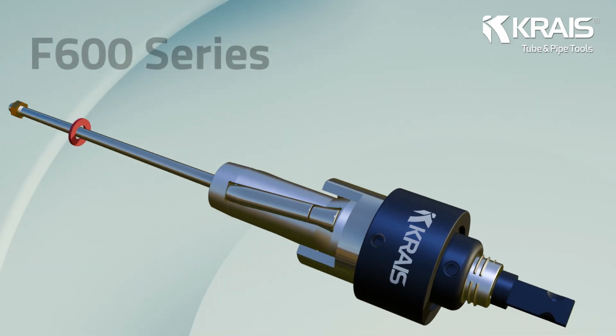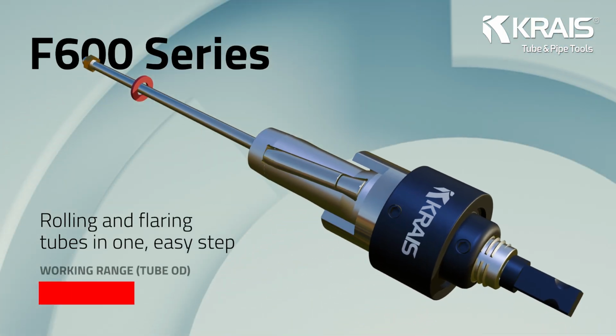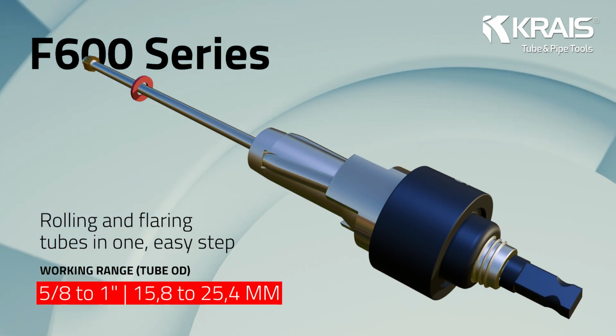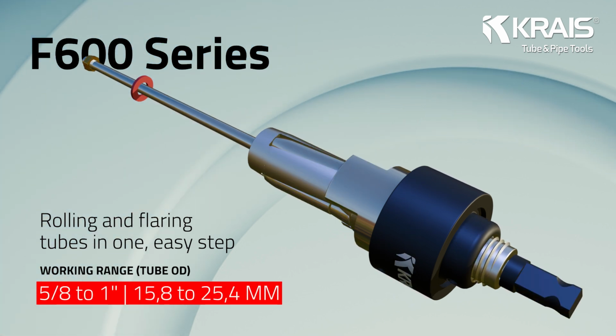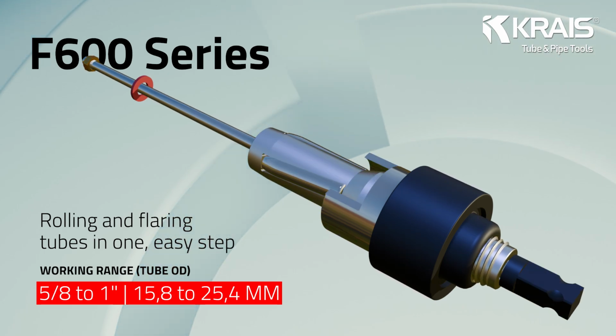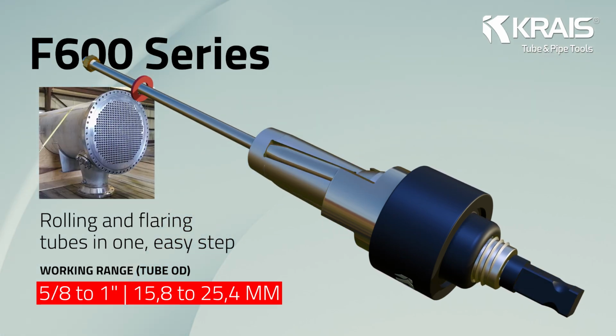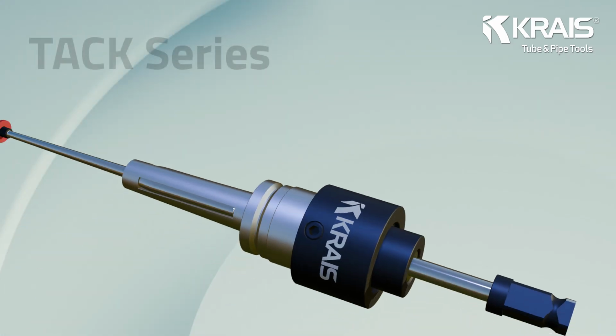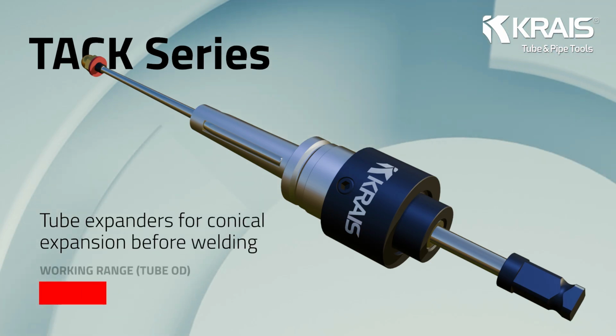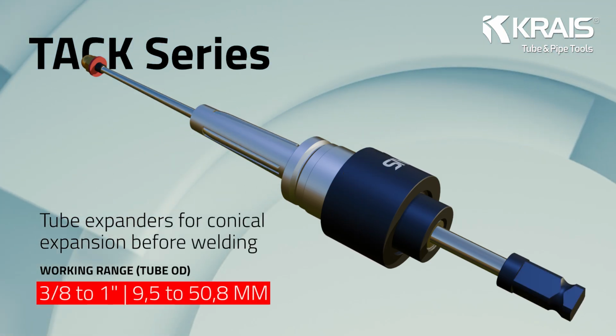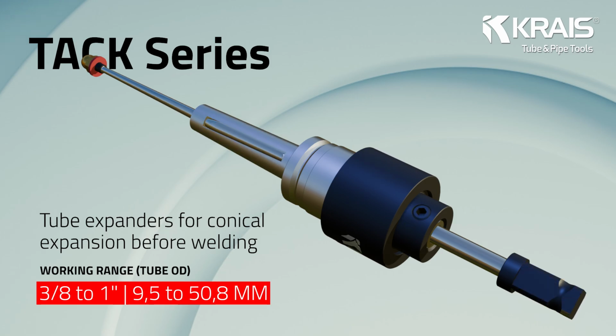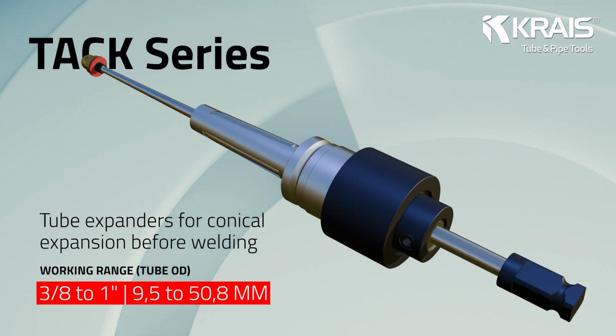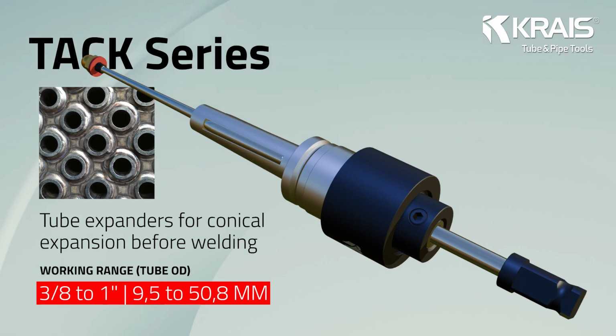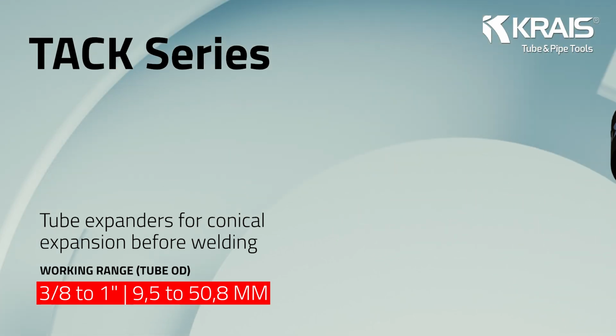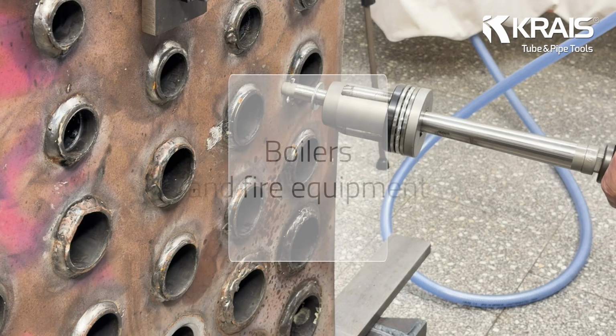The KRAIS F600 series performs tube expansion and end flaring in a single operation. Use it where the specification calls for a flared tube end as a mechanical feature, or where you want to avoid variability associated with a separate flaring step. The KRAIS TACK series delivers short, controlled, conical expansion as preparation for welding. It is used in rolled and welded joints to remove clearance, stabilize the tube, and improve weld conditions. The conical profile provides maximum expansion close to the tube end.